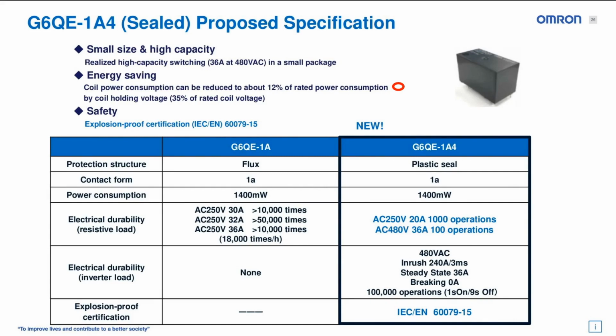This product, again, will be plastic sealed. It is a 1form-A relay. And then our ratings are really tailored to inverter type loads, but we are always open to test for different ratings that are required by our customers. So the general ratings for resistive load will be 20 amp 250 VAC for 1,000 operations and 36 amp 480 VAC for 100 operations. And in terms of the inverter load, which is what we're developing this for, it's 480 VAC, 240 amp inrush, 36 amp steady state, and breaking at 0 amp. So breaking with no current. That's for 100,000 operations.